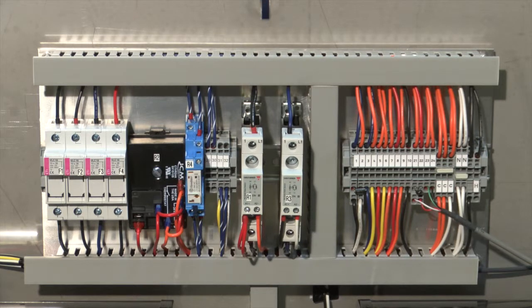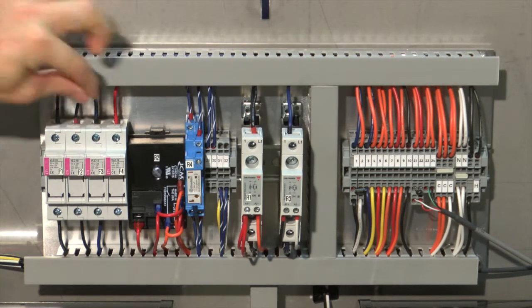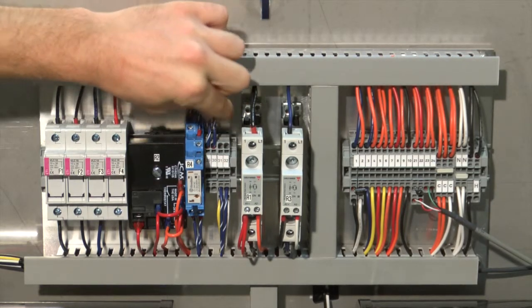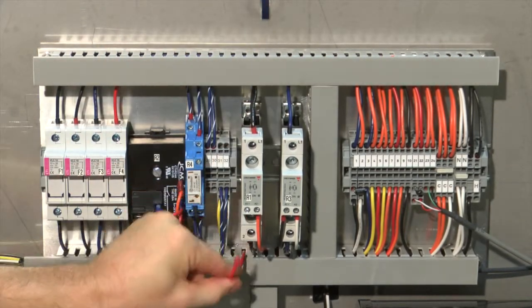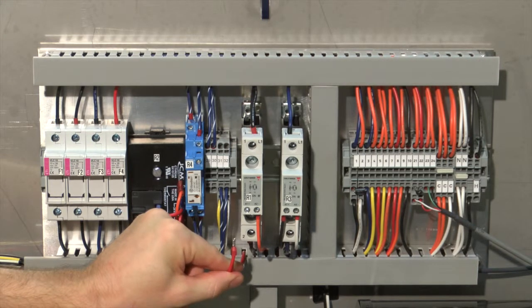Sometimes the simplest solution is the correct one. A loose wire can keep a relay from being energized and the system from working correctly. This can sometimes happen on a brand new system, as sitting on a truck during shipping can loosen electrical connections. When starting up a new system or troubleshooting a system not working correctly, it's a good idea to just check the tightness of each electrical connection, as all it takes is one small loose connection for the system to not work correctly.